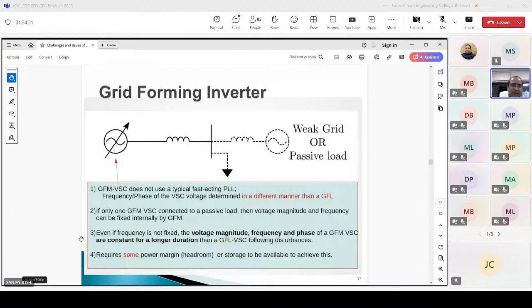But in a grid forming inverter, even if the frequency is not fixed, it is varying. The variation is of course low, but it is not constant. The voltage magnitude, frequency and phase of a grid forming VSC are constant for a longer duration than a grid following VSC following a disturbance. So here there is a comparison for a given disturbance, right? The same kind of disturbance is given to the grid forming inverter and the grid following inverter. In that case, these quantities, voltage magnitude, frequency and phase, are constant for a longer duration compared to GFL. Grid forming inverters require some power margin or storage to be available to achieve this, which I have mentioned in point number 4.